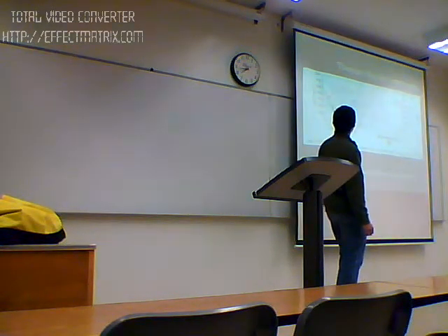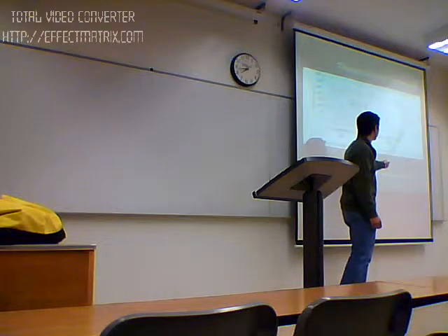On this left-hand graph, we're mostly concerned with this blue line, which indicates COD. You can see you start off on both ends with around 6,000 milligrams of COD per liter, and on both ends they end up at roughly 500 milligrams of COD per liter. But what's interesting is the x-axis, which corresponds to hydrogen peroxide consumed.